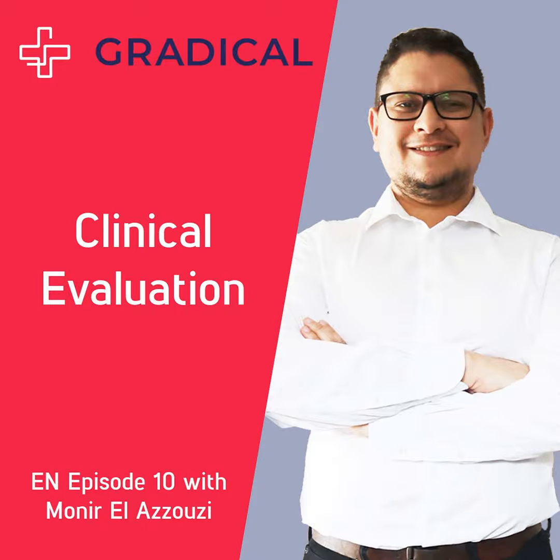So they try to understand, they don't understand, so they ask you to re-explain maybe this part, or to re-emphasize this thing, etc. So you'll get also some non-conformities from notified bodies about your clinical evaluation. If you don't get any, I mean, you are really lucky. But if you get them, no worry, it's normal. But you should spend most of your time during the certification on your clinical evaluation.